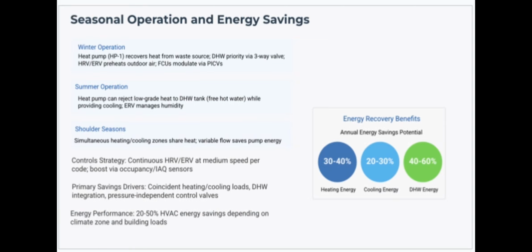Heat pump in the winter: the heat pump recovers heat from the waste source, DHW priority via three-way valve, HRV, ERV prevents or preheats outdoor air. FCUs modulate via PICVs. In summer operation, the heat pump can reject low grade heat to the DHW tank, free hot water, while providing cooling, and the ERV manages humidity. And in shoulder seasons, due to it being cold in the morning and hot in the afternoon/evening, simultaneous heating/cooling zones share heat, variable flow saves pump energy.